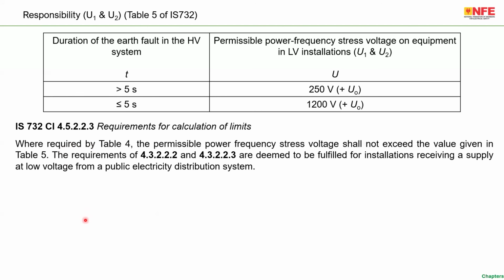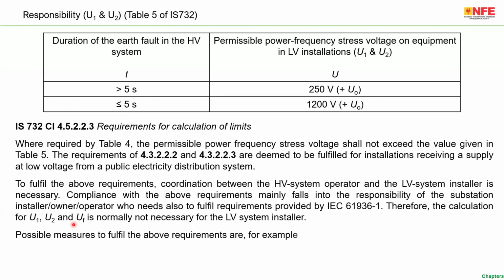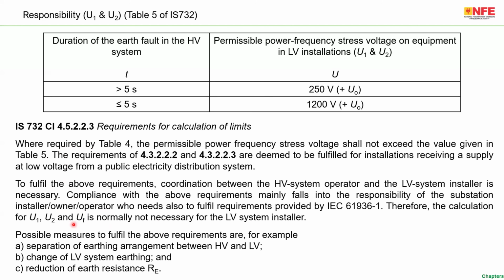Now, the standard IS 732, clause number 4.5.2.2.3, explains who is responsible for limiting this voltage. Please note that for limiting this voltage to less than, for example, in a solidly earthed system with less than or equal to 5 seconds, 1200 volt, the consumer cannot do anything. The consumer is helpless in this particular case. It is the owner of the transformer who is supposed to limit this voltage. If the transformer belongs to the distribution company, then the distribution company should ensure that the maximum transferred potential due to EPR is limited to less than 1200 volt. If the disconnection time is more, of course, 250 volt, because the connected equipment cannot withstand more than this voltage.